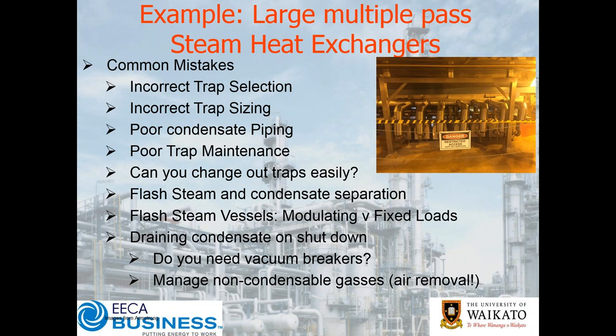The other key thing with these applications is what happens to the condensate when you shut down. When you shut down, you've actually got to drain that away. When you shut down, the steam valve shuts off, steam condenses, and your coils can actually be under vacuum — and if they're under vacuum, they're not going to drain away.